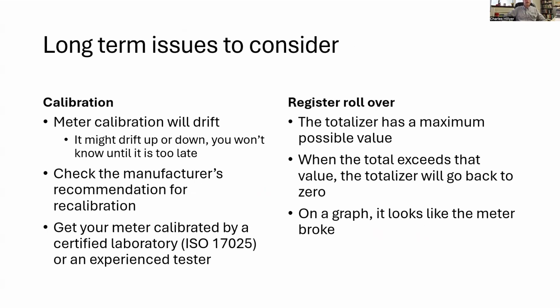The last thing I want to mention is some of the long-term issues. These flow meters that are appropriate for the MAGS metering program are built to last quite a long time. And calibrations do not last forever. Every meter, no matter how good it is, will have calibration drift over time. The manufacturers are going to have some recommendation somewhere in their product literature telling you how long they recommend you wait before you get your meter recalibrated. It varies by measurement type. It also varies by manufacturer. It's not something you need to do necessarily every year, but again, that depends on the meter type itself. But you will eventually need to get your meter recalibrated.